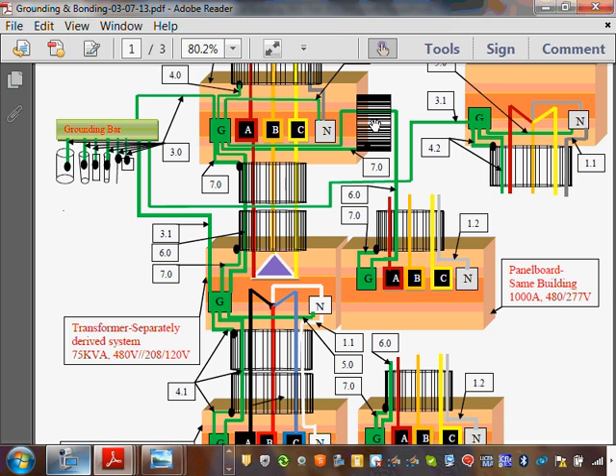Now when you bring your conduits to the bottom of your switch gear, you need to ground your conduits to the switch gear. There are different options of doing that. If it's coming to an open bottom switch gear, you're popping out of the concrete and the switch gear is sitting right at the top of it, you can't tie metal to metal, can you? There's nothing metal to metal to tie. So the only option that you have right here to ground that conduit is something called a bonding bushing. That's option number 1. Works all the time. Option number 2, if you're coming to the bottom of the conduit through a hole in the box, so you can't put metal to metal, then the conduit connection, the lock nuts, will do the bonding for you. You don't have to worry about that. This is bonding the equipment, not at the service.